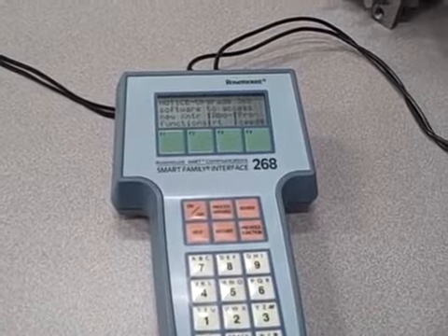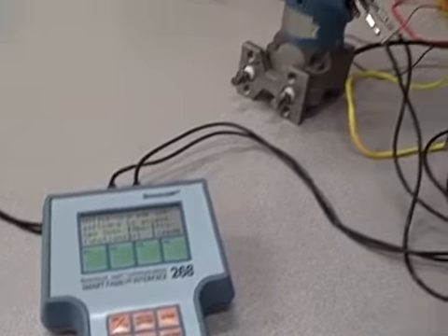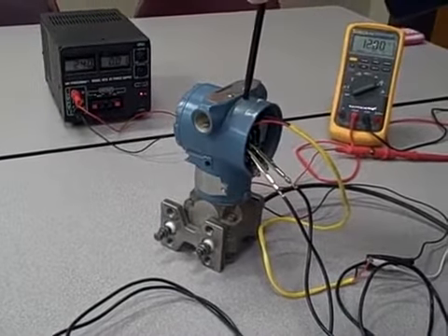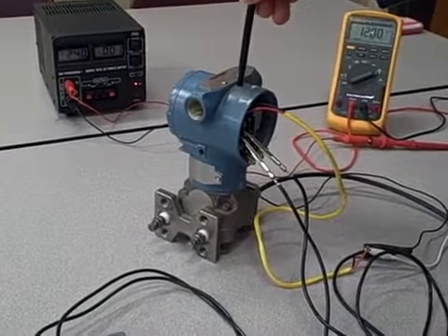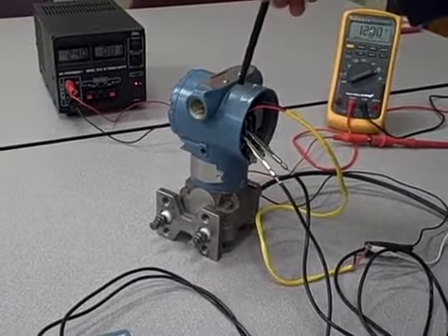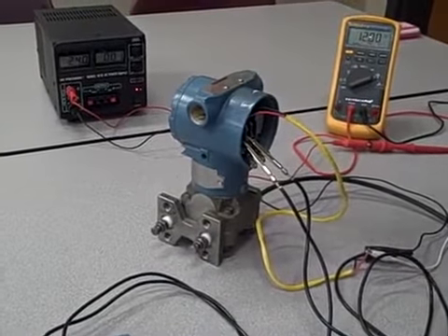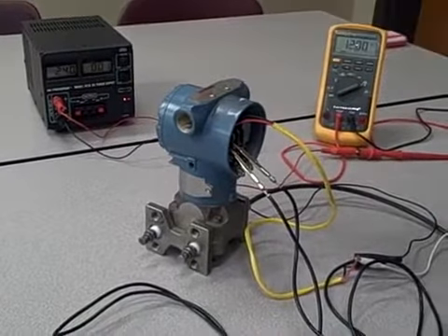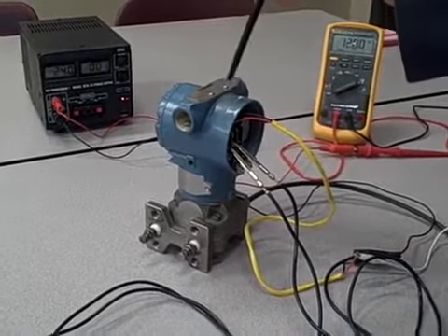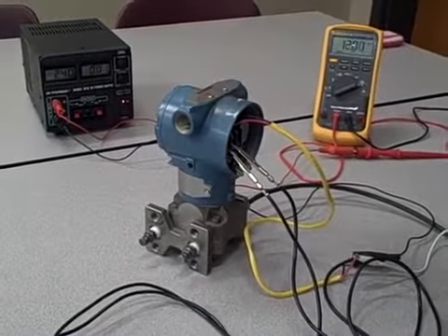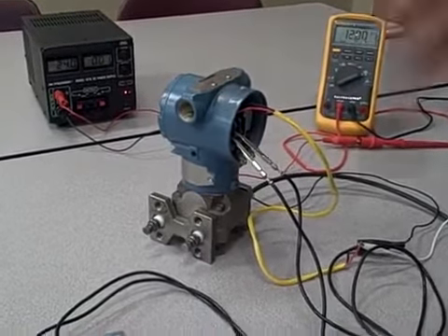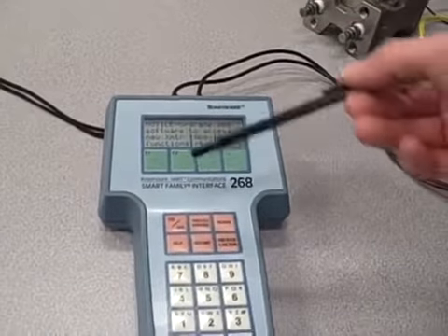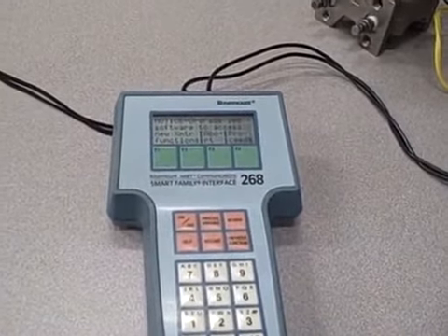Likewise here, these smart field instruments are so varied with so many different features and functions that the device description files, the driver files needed to talk to these, will change over time. So for example, if I were to get a newer model of this transmitter, it would require a different DD file than this model right here. Well, that can be a problem for the HART communicator because if you don't upgrade it with the necessary DD files, it doesn't know how to talk to the newer transmitters.